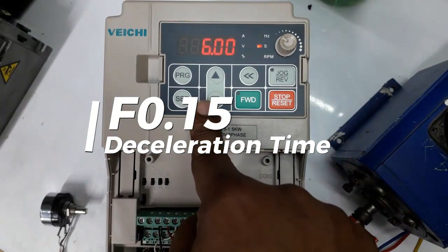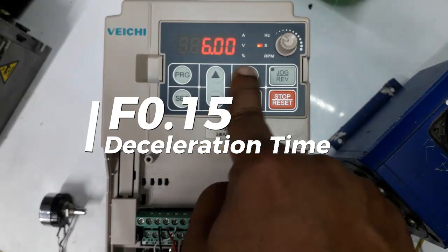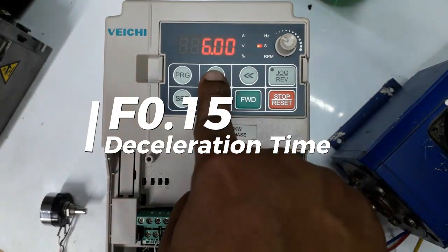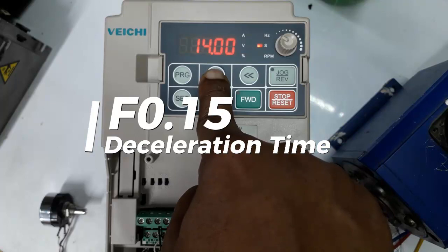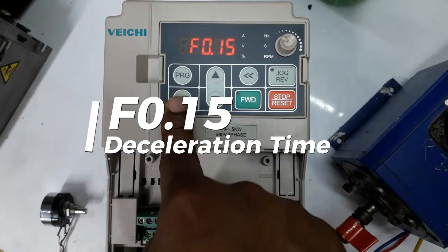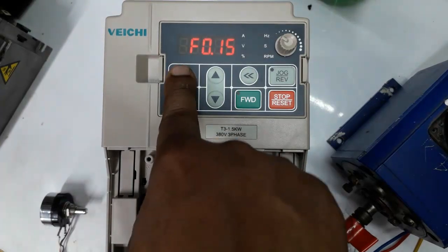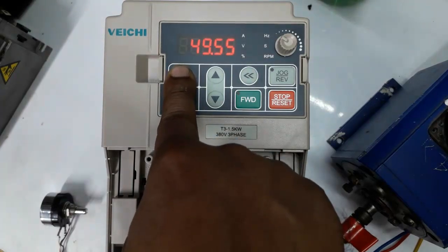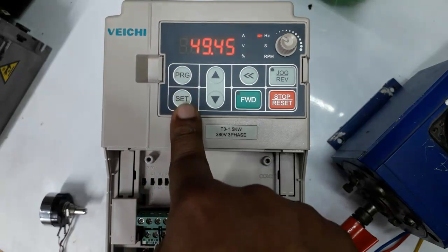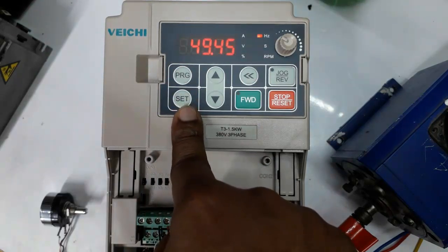F0.15 is for deceleration time. We set it here to 20 seconds. That's when the motor will be stopped from maximum frequency to minimum frequency within 20 seconds.